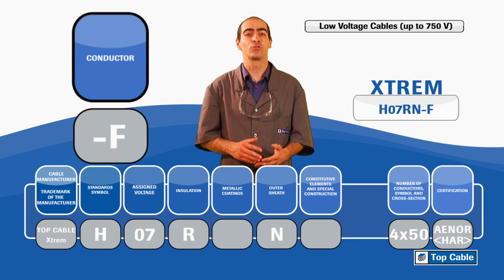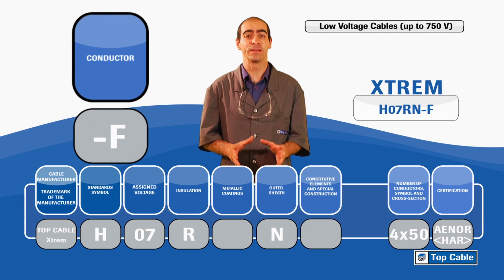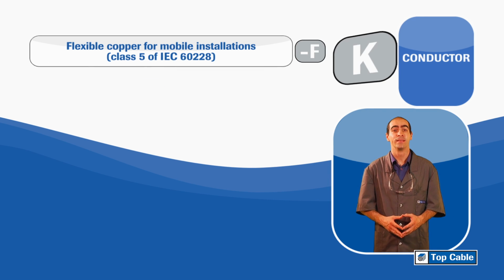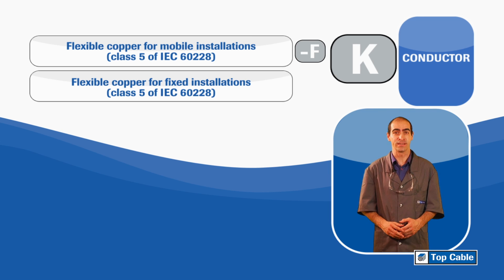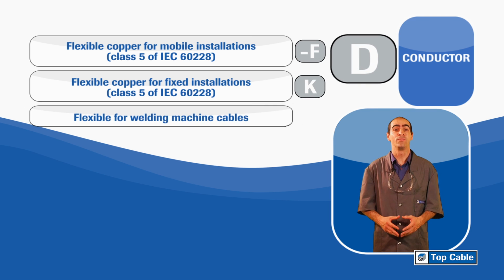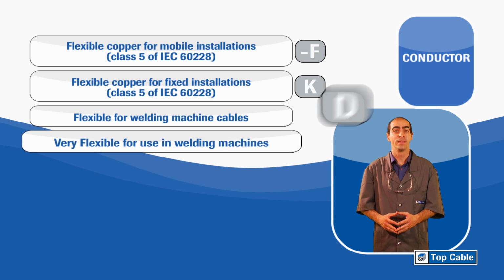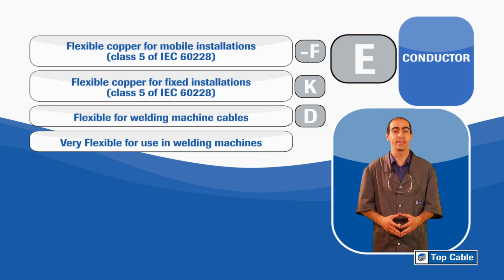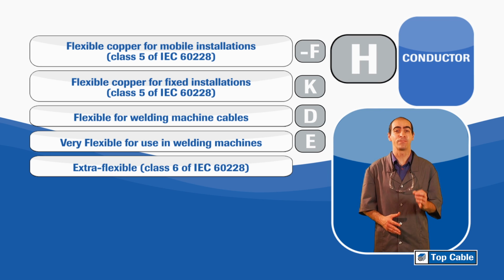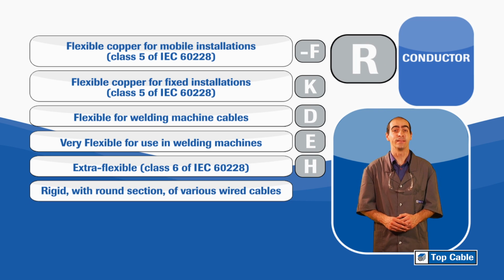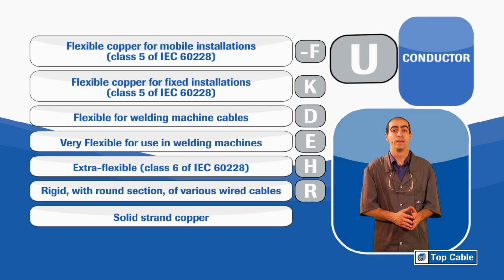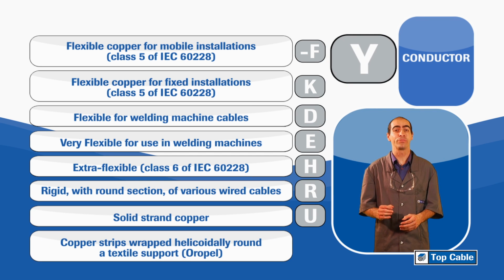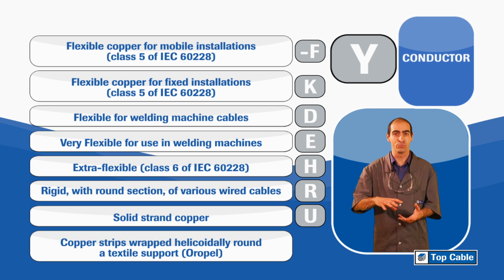F means that our cable is made up of flexible copper, class 5 of IEC 60228, for use in mobile installations. Other common conductors are K, flexible copper for fixed installations, class 5 of IEC 60228. D, flexible for welding machine cables. E, very flexible for use in welding machines. H, extra flexible, class 6 of IEC 60228. R, rigid with round section of various wired cables. U, solid strand copper. Y, copper strips wrapped helicoidally round a textile support, tinsel.